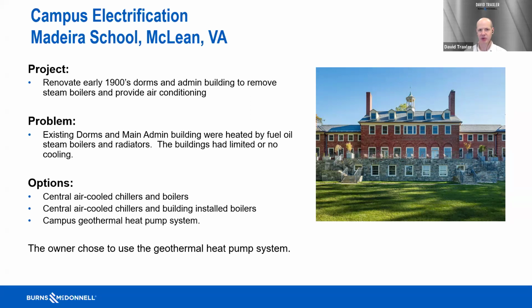They also wanted to put cooling in these dormitories so they could be used year-round for summer camps, with air conditioning in early fall, late summer, and late spring, when it can be hot and humid in the DC area. The options considered were a central air-cooled chiller with piping to the buildings, central boilers with piping to the buildings, a central air-cooled chiller with building-installed boilers, and a campus geothermal heating and cooling system. The owner chose geothermal, both for aesthetic reasons and for sustainability.